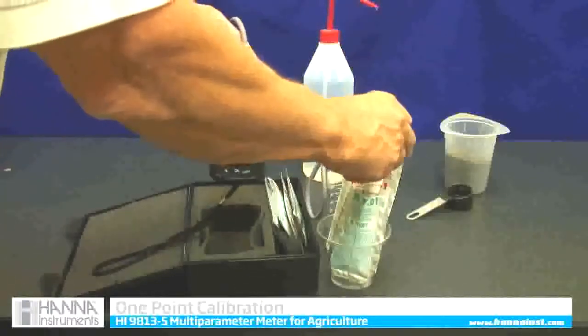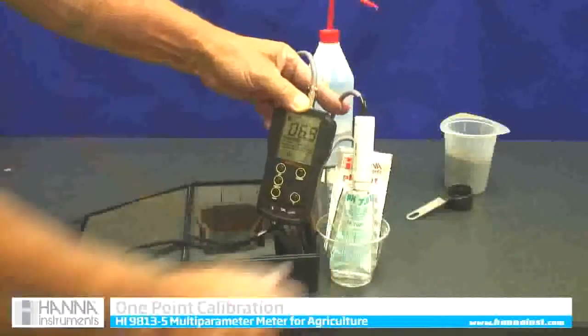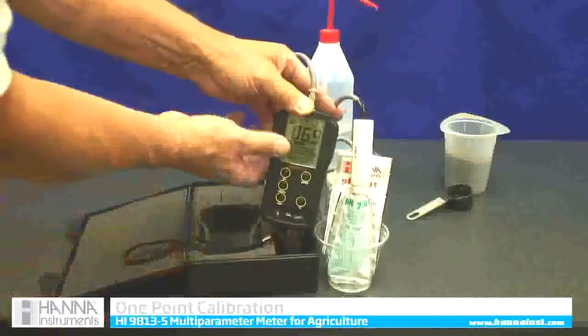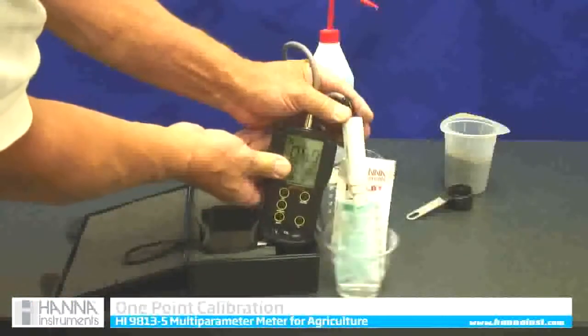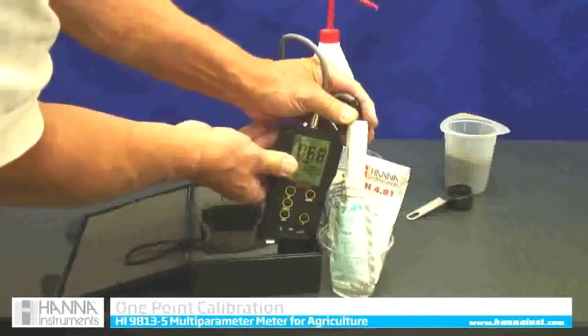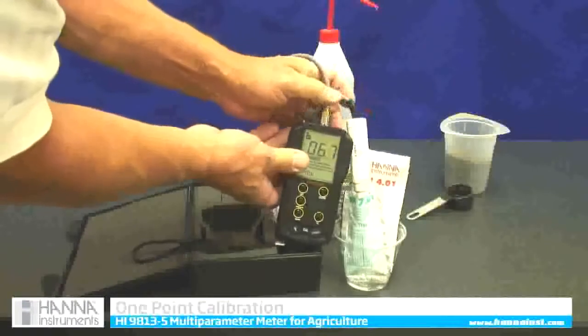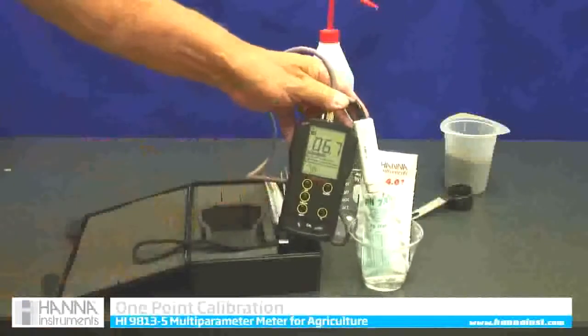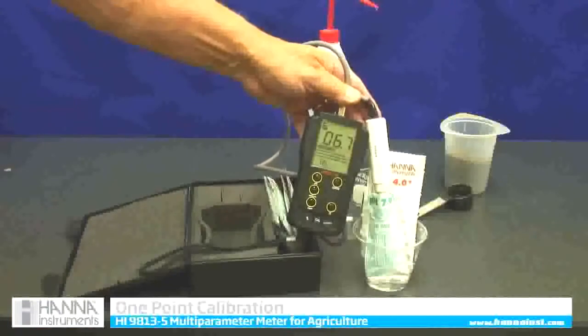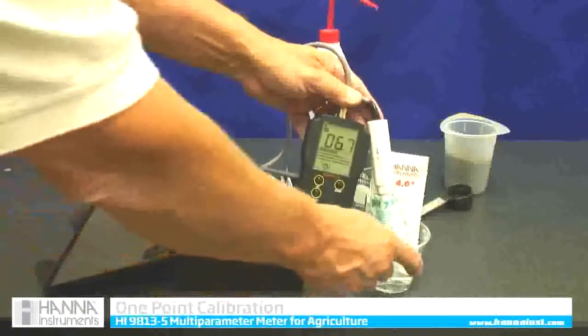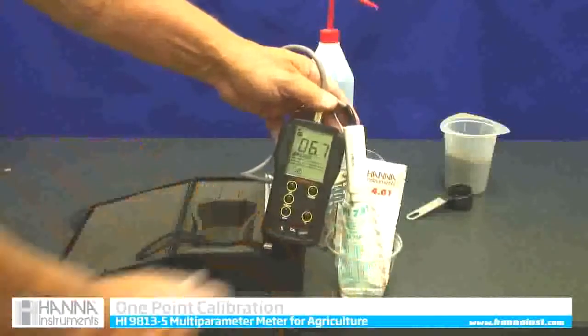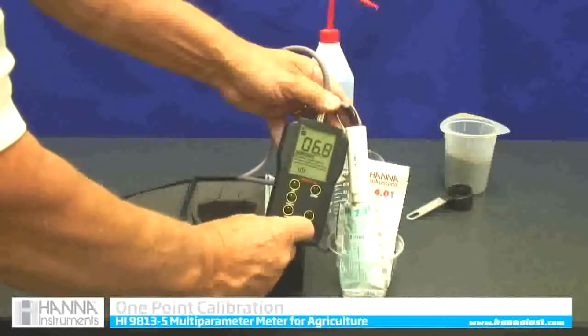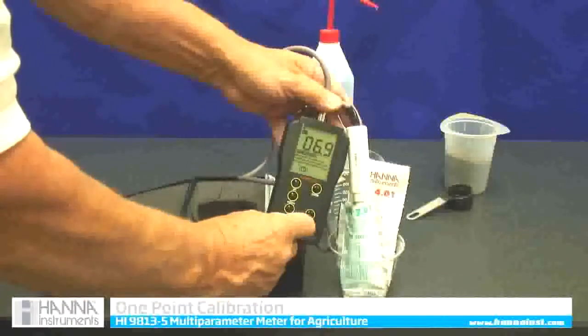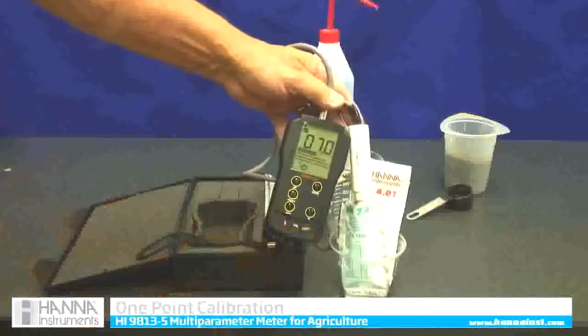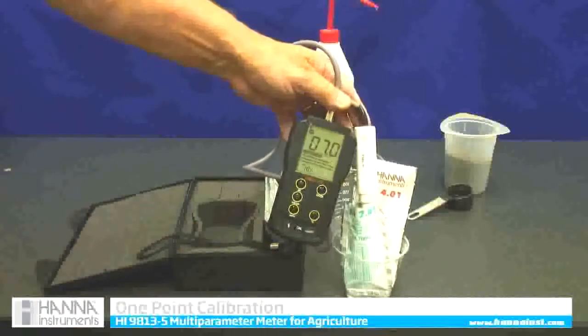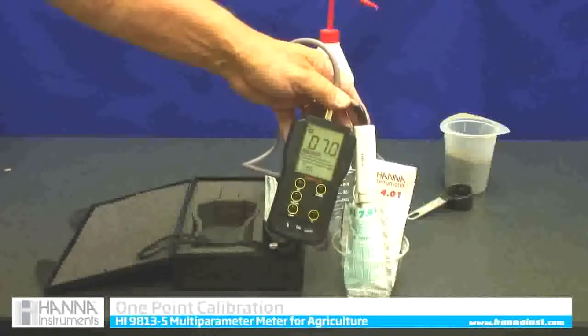So we're going to insert the probe directly into the pack. I'm going to swirl it around a little bit to make sure that it's in contact with the calibration solution. And you can see I'm reading 0.67. That means I have to adjust it. That easy. Now I'm in calibration. So now I can do a soil test.